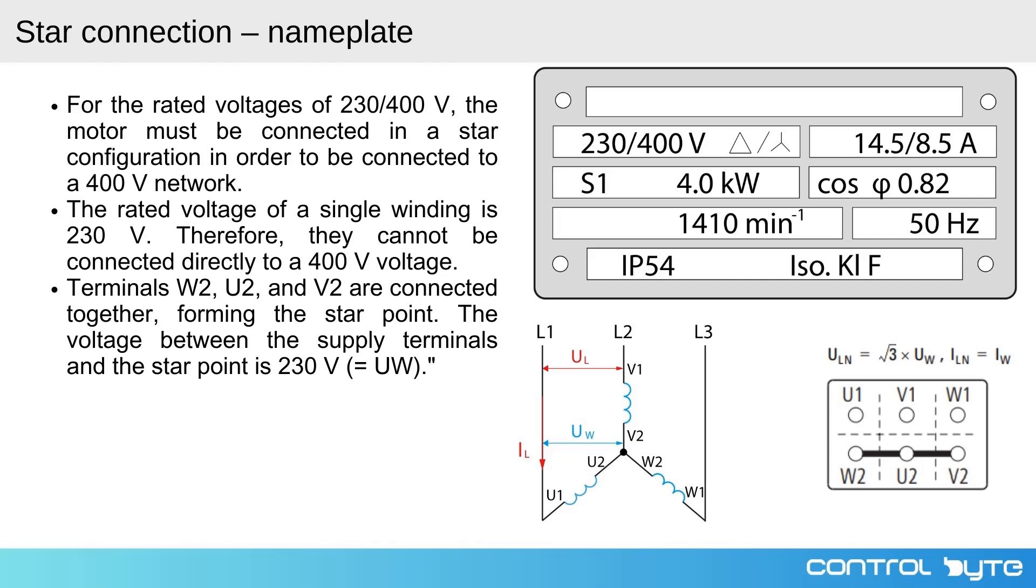Let's look at this motor's nameplate. Here we see the voltage ratings listed as 230/400 volts. This indicates that for the motor to operate correctly on a 400 volt supply, it must be connected in a star configuration.